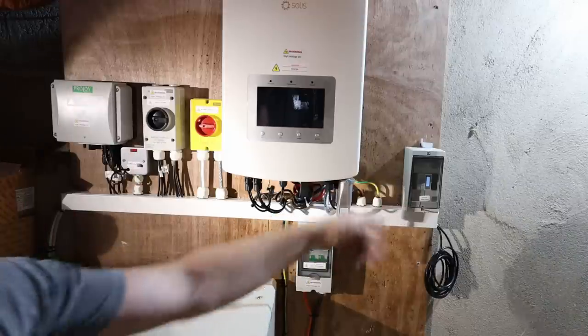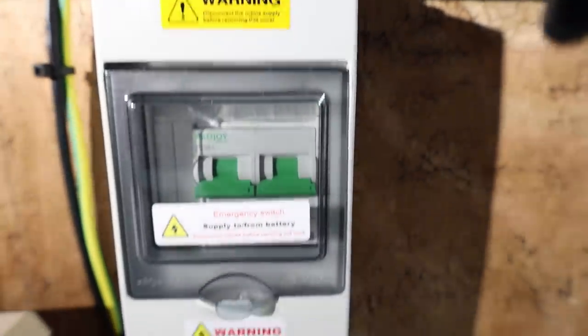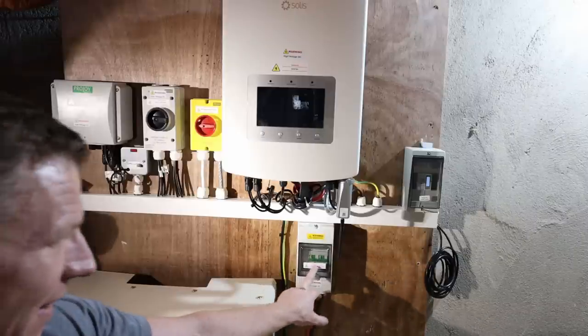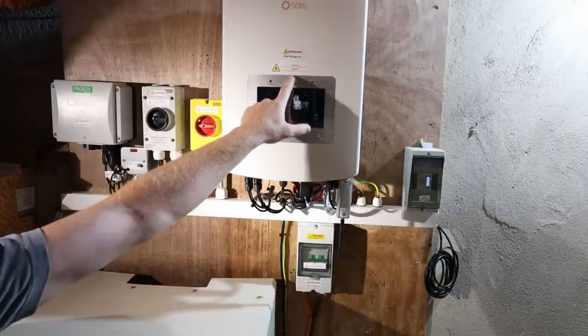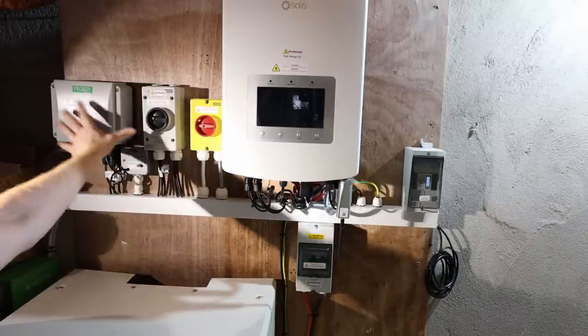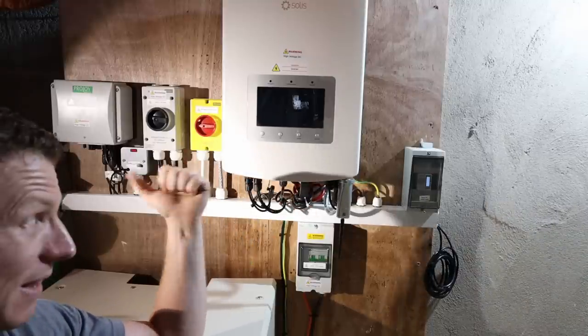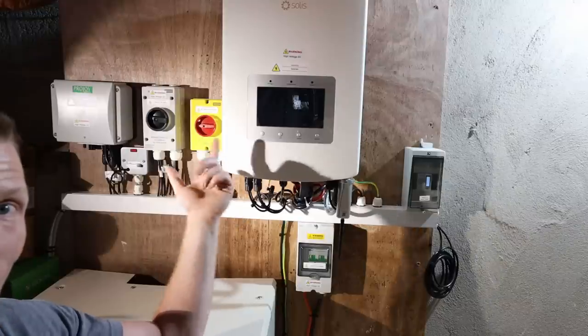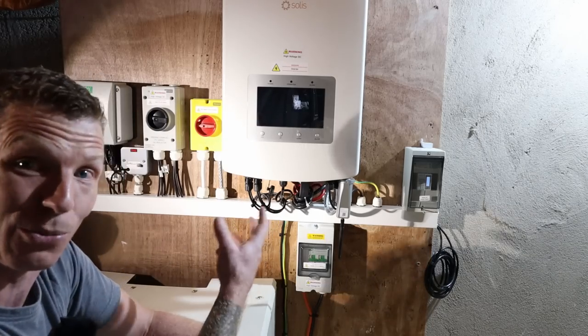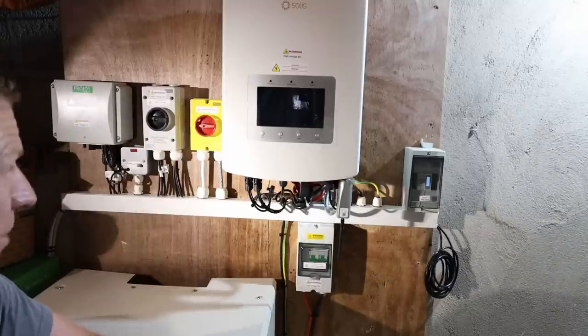I have a cable over to a small kilowatt-hour meter where I can look at all my information. Down here is the isolation for the battery — a 125-amp breaker for the battery connections, all DC. Everything is labeled with stickers: high voltage DC warning, AC supply kill switch, solar panel kill switch. The fuse board in the house must also be labeled — you must let everybody know there are now two supplies to your consumer unit from both solar panels and the grid. The meter cabinet outside must also have a sticker with details of where all the emergency isolation is.